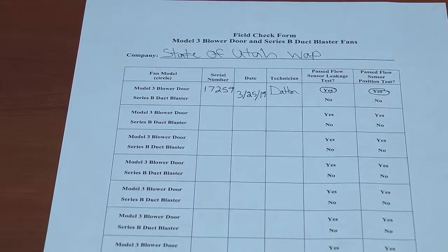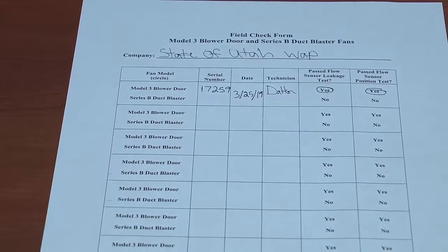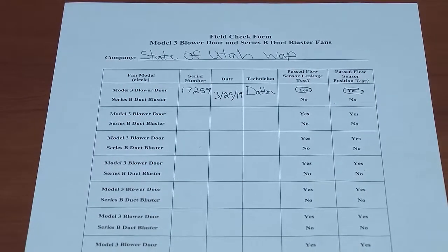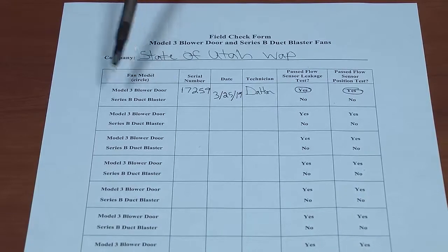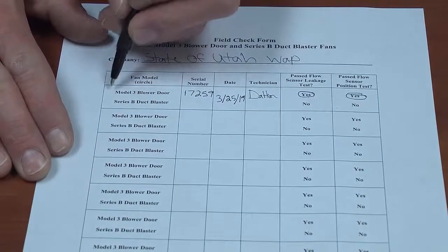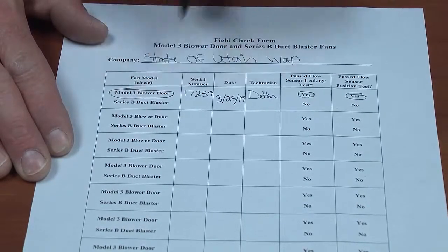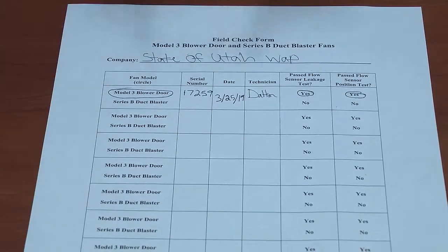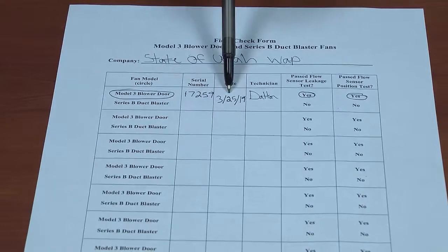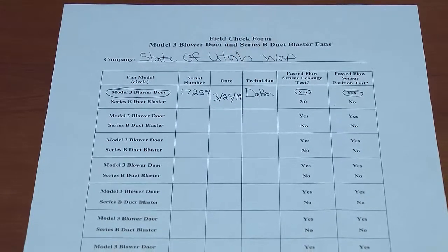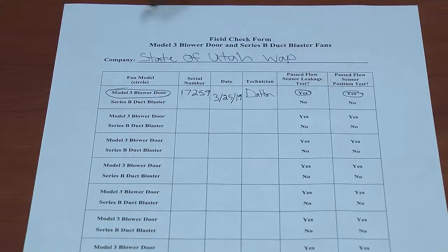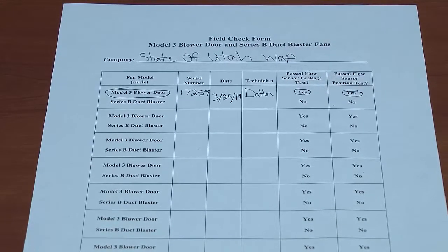All right, so the Energy Conservatory has a form to track when you're inspecting your equipment. You want to circle, like we just did, the blower door. So you want to circle what equipment it is, the serial number, the date you performed the inspection, the technician that inspected it, and if it passed the leakage test, and if it passed the position test.